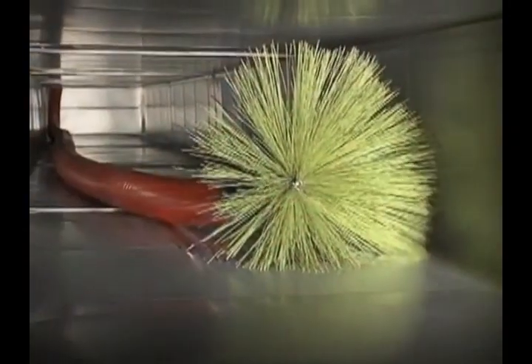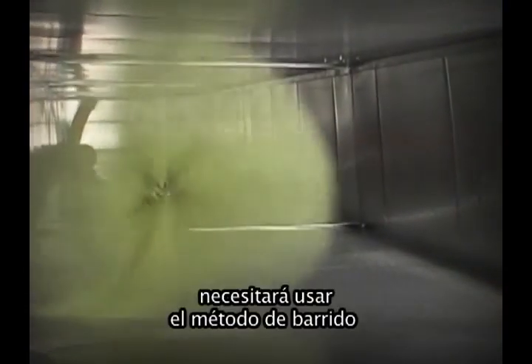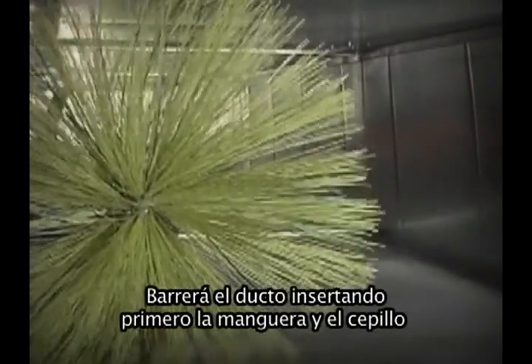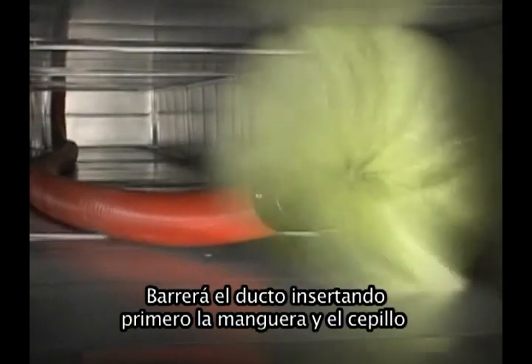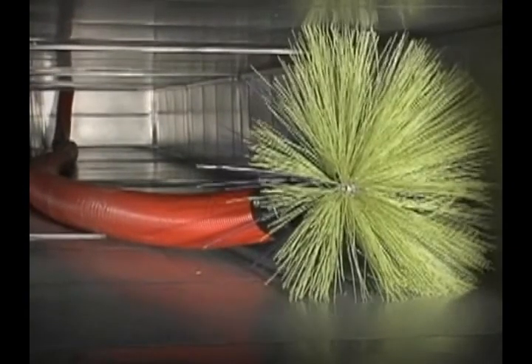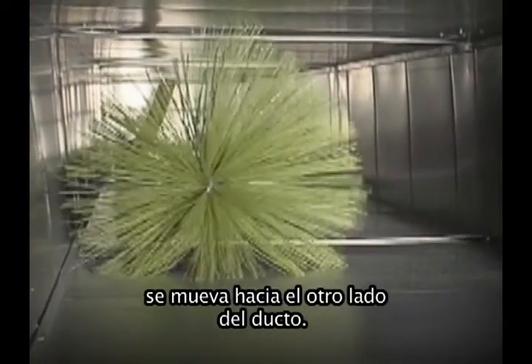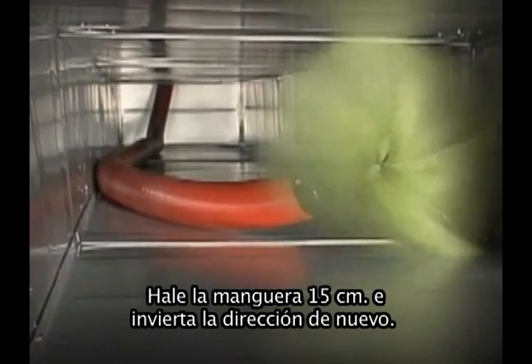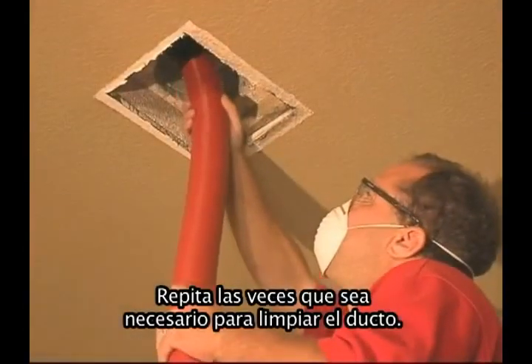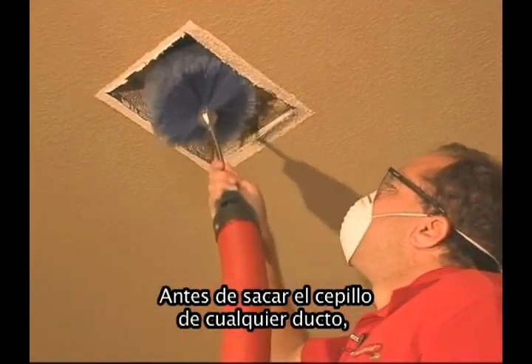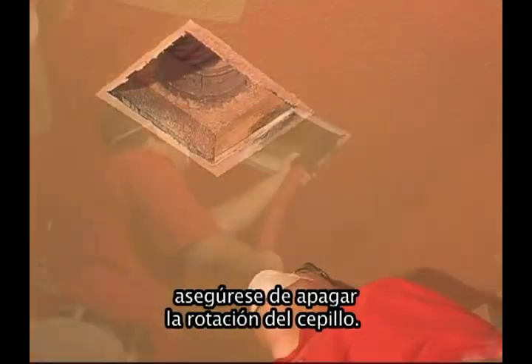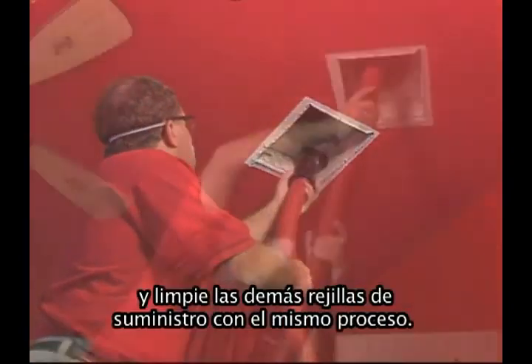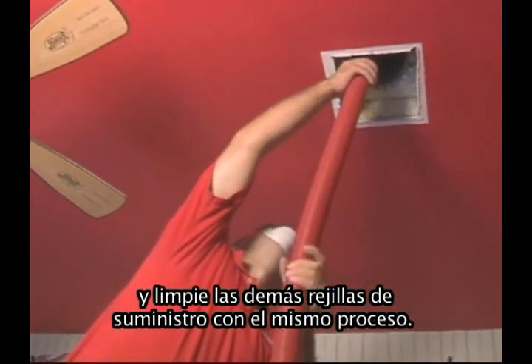Now, if you're cleaning rectangular ductwork, you need to use the sweeping method to ensure that you're cleaning all sides of the ductwork. You will sweep the air duct by first inserting the brush and the hose all of the way down the duct line. Then reverse the brush rotation to cause the brush to travel towards the other side of the duct. Pull the brush back about 6 inches and then reverse the direction again. Repeat as needed to clean the length of the duct. Prior to removing the brush from any air duct, make sure you turn off the brush rotation. Move on to the other rooms and clean the remaining supply air ducts using the same process.